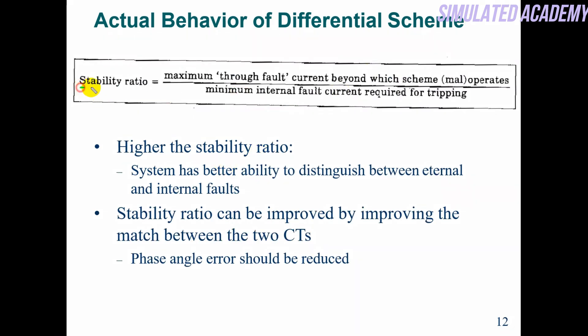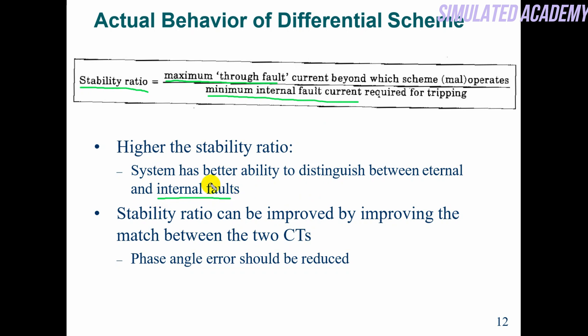Stability ratio is defined as the maximum external fault current divided by the minimum internal fault current. This is called stability ratio. The higher the stability ratio, the better the system's ability to distinguish between external and internal fault currents. The stability ratio increases when the external fault value is high and the internal fault detection value is as low as possible. Stability ratio can be improved by improving the match between the two CTs.